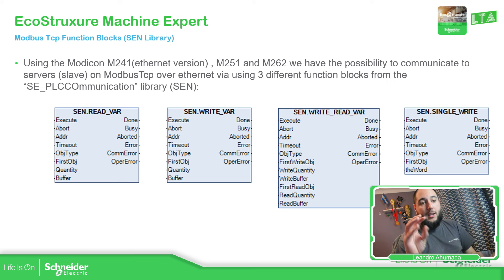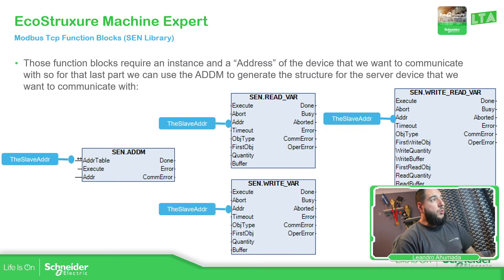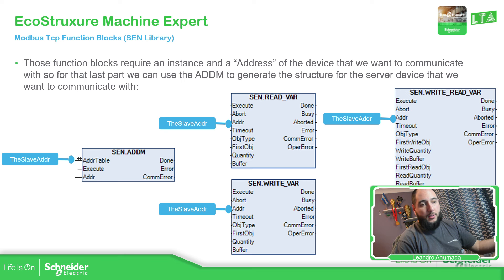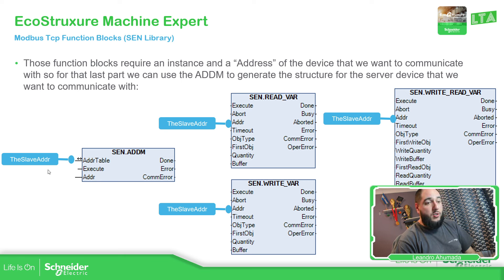All these function blocks require an instance — it's a function block, not a function. So in order to use them, what we need is to have a structure that is generated by using the ADDM. If you don't want to use this, you can just create your structure and manually add the things in there if you have more experience. Otherwise, you can use this ADDM to generate this structure. It has an input and output — you put information in the address, give the execute, and it generates the information you need to use in these function blocks.